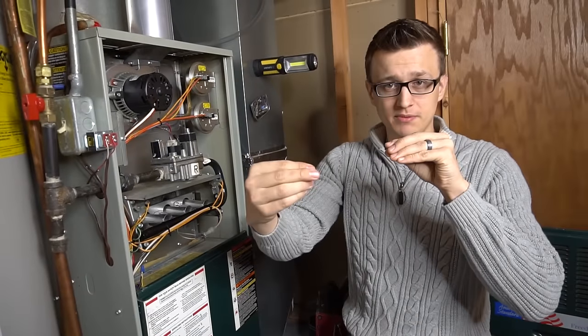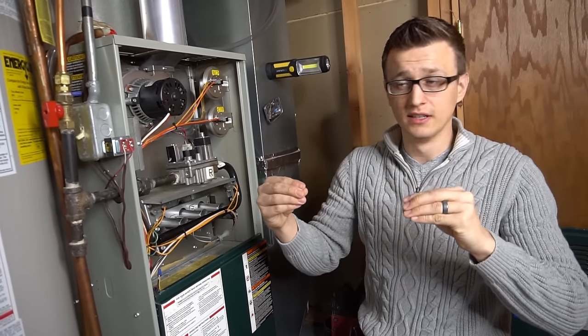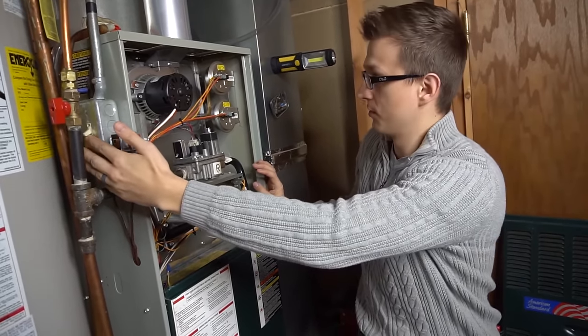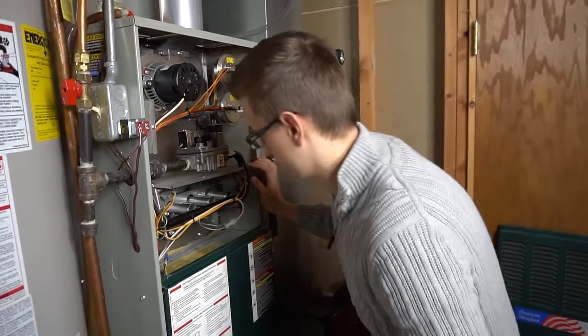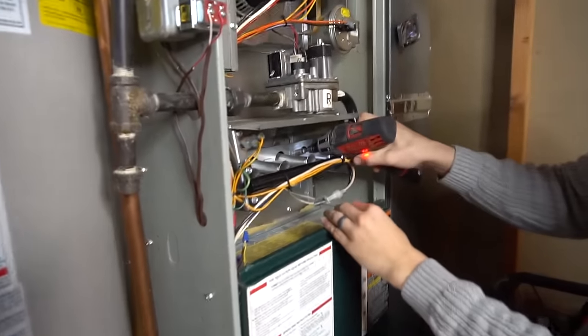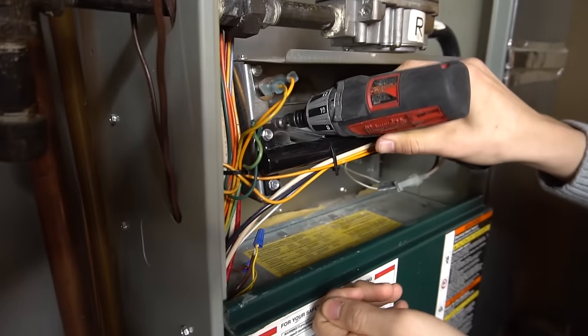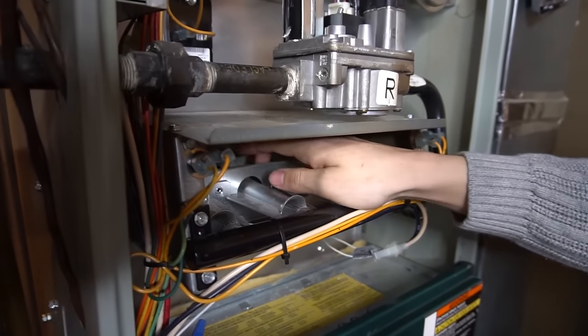Your flames should be cone-shaped and just getting sucked right in. Let's just look at my furnace here. I'll turn the power switch back on and take my little retaining bracket off so you can see my flames better.